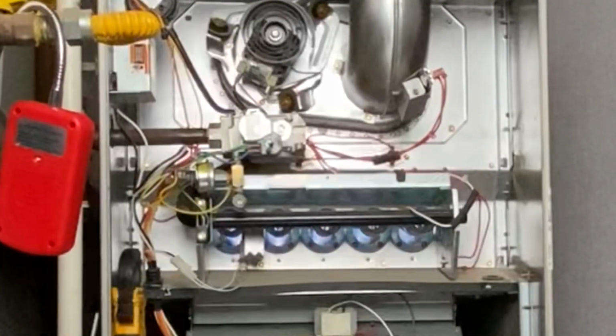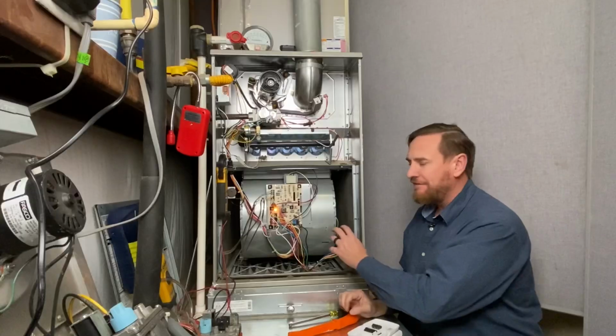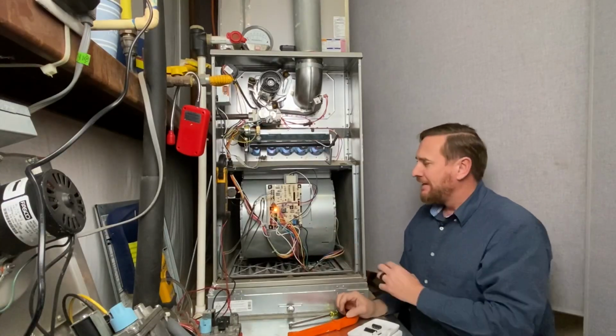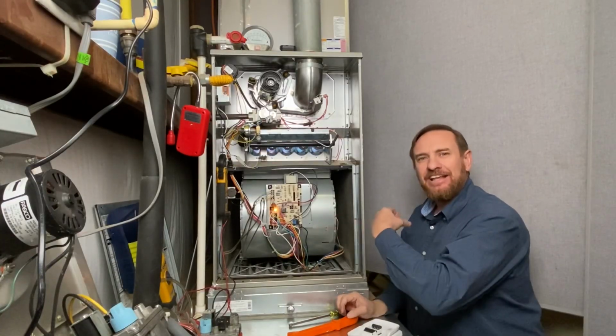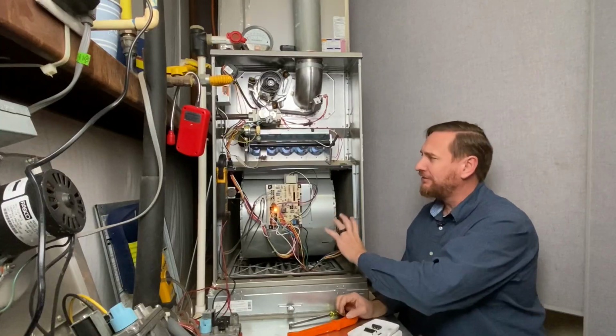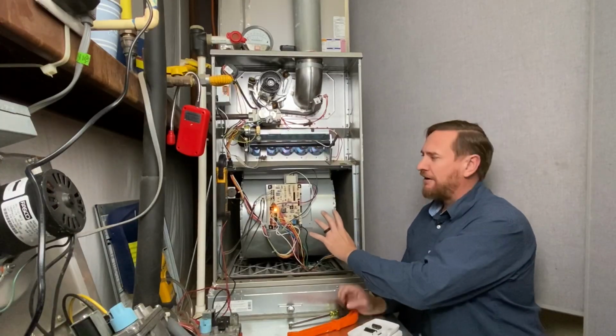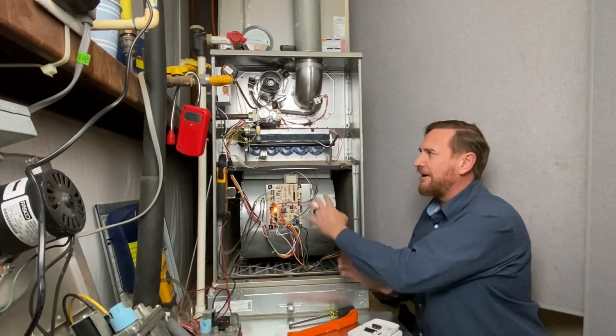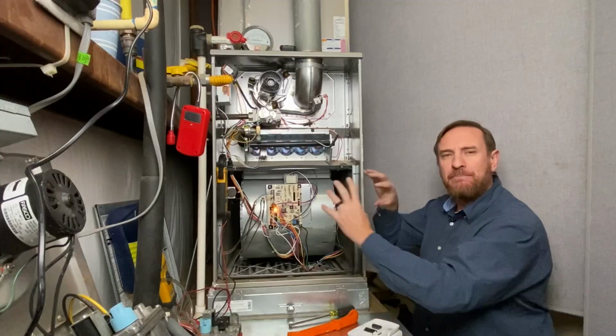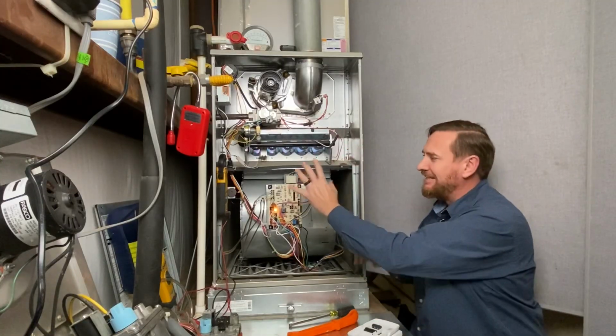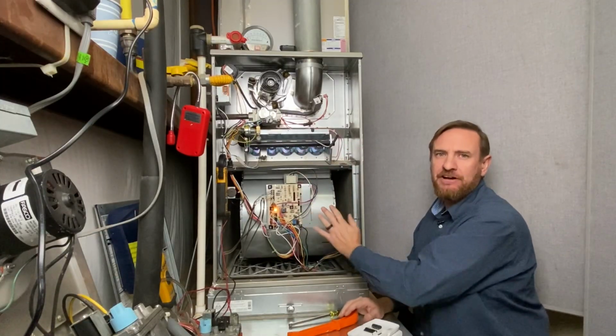Now, a few things I want to point out: I have this door off right now, we're going to zoom back out. That's not good. Just for test purposes we can do this, but you never want to have this door off because the blower is actually pulling air from the burner compartment. The combustion air of the furnace needs to always be separate from the airflow of the house.